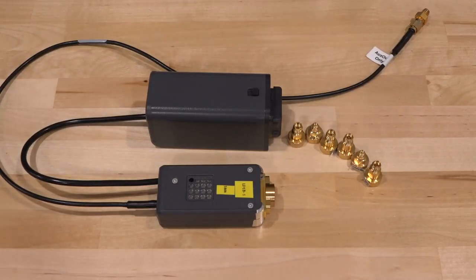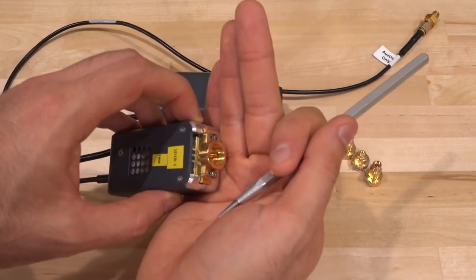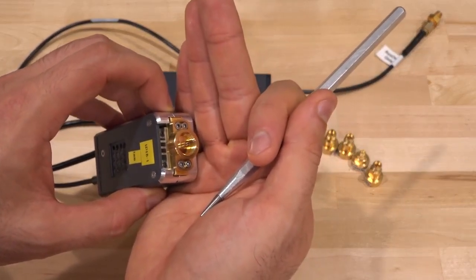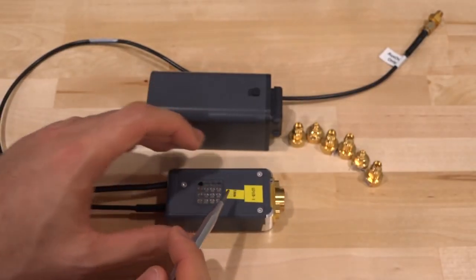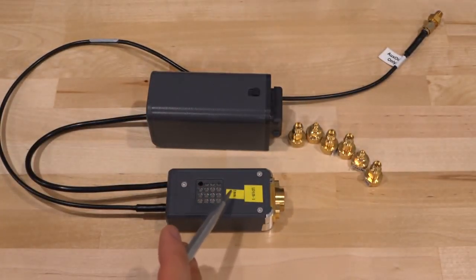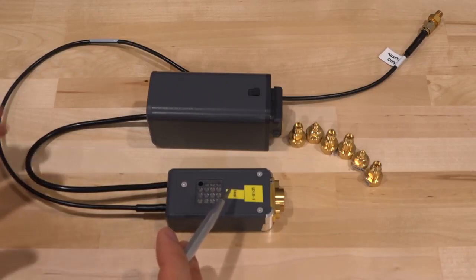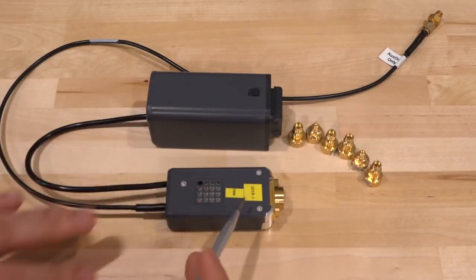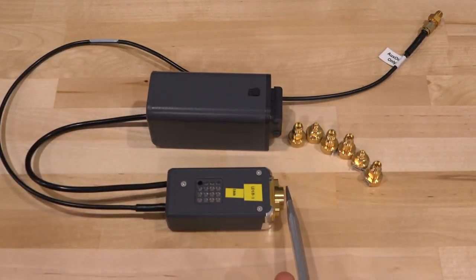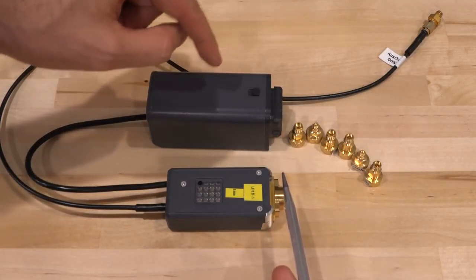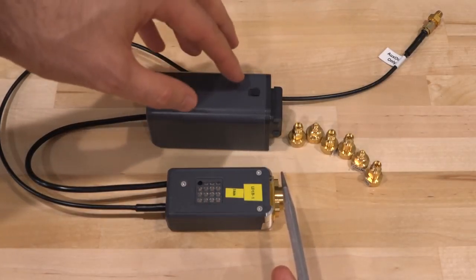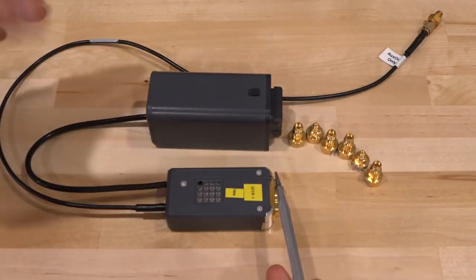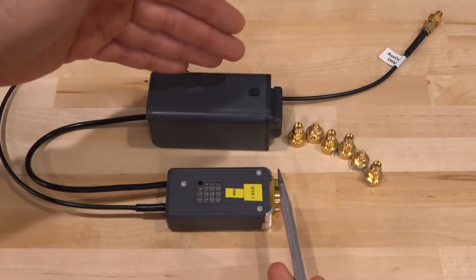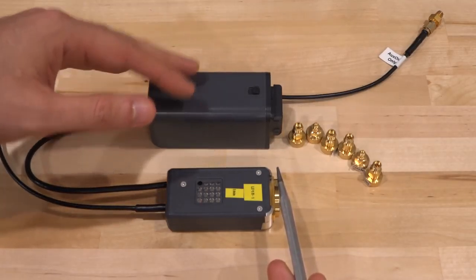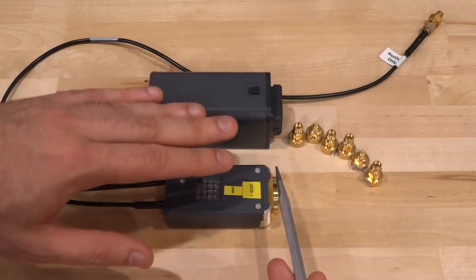And here's a close look at the calibrator. The front end of the calibrator directly mates with the front connector of the unit. It's a 1mm ruggedized connector, and everything in this module is designed by Keysight. It has their own 3.5 process components in it, and I will show you from a photograph how it works. Now, as I said, this is a NIST calibration unit, meaning that the exact response of it up to the edge of this connector is stored in here. Once you connect this to the unit, it will download this response into the instrument, and the instrument will try to match this response from the measurements it's getting. So it doesn't even matter what that response is, as long as it has enough frequency content to meet the 110 gigahertz requirement. That's pretty clever and a good, simple way to do this, as long as you can create this device, and I'll show you what that is in just a second.